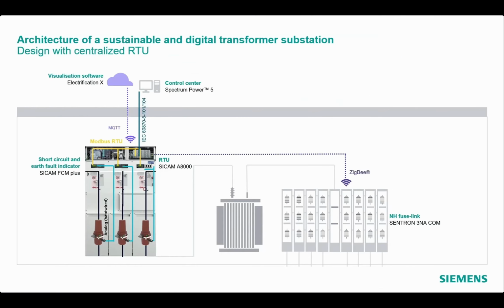Next to the measurement of current and voltage on the medium voltage side, a measurement of the currents from the low voltage distribution provides a more precise grid monitoring. In addition to new digital transformer substations, also existing ones are to be retrofitted easily with low voltage current measurement. The use of smart fuse links type SENTRON 3NA COM is therefore useful for this purpose. This communication-capable fuse has the same dimension as a conventional fuse link and can be easily used in existing fuse bases. Thanks to its wireless communication, it involves no additional wiring effort for the data transfer to the gateway in the digital secondary substation.